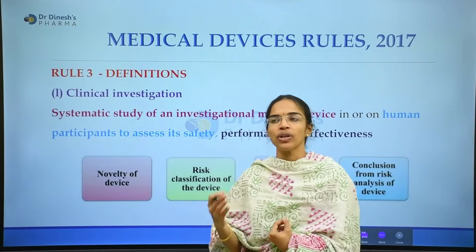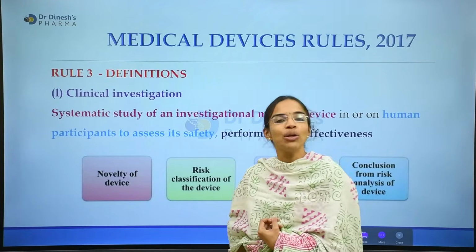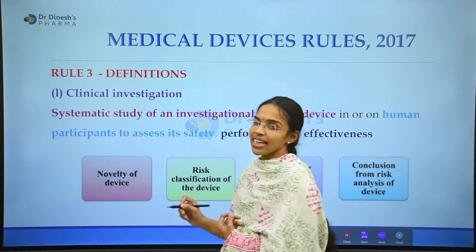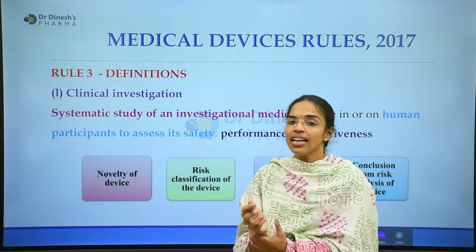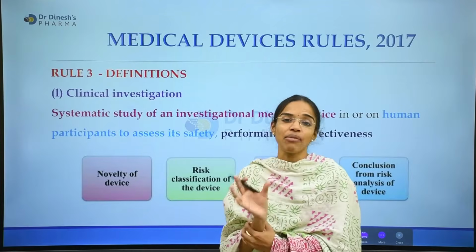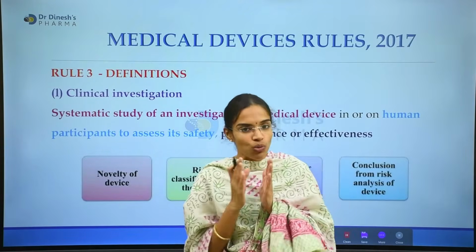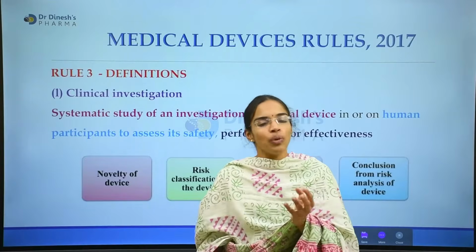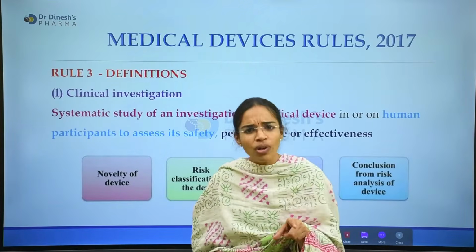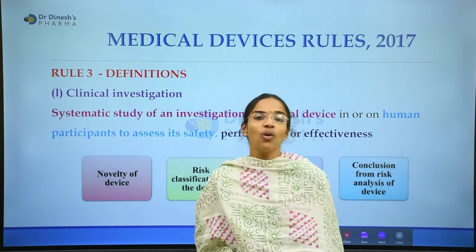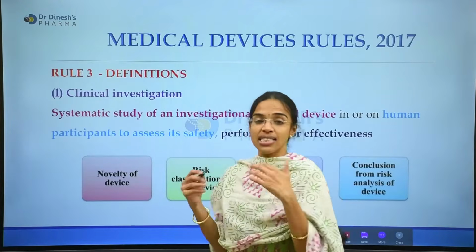What is the difference between a clinical evidence and a clinical investigation? Investigation, the name itself says, is a systematic study of the investigational medical device, whether it has already been approved or is going for approval.